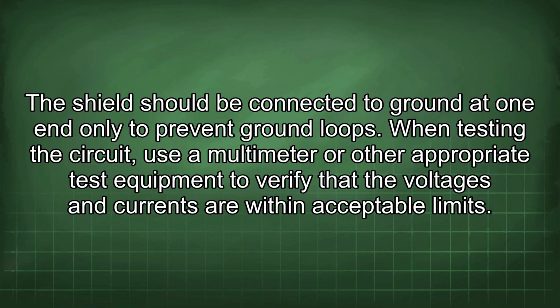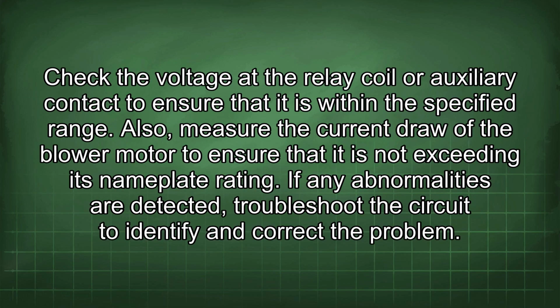When testing the circuit, use a multimeter or other appropriate test equipment to verify that the voltages and currents are within acceptable limits. Check the voltage at the relay coil or auxiliary contact to ensure that it is within the specified range. Also, measure the current draw of the blower motor to ensure that it is not exceeding its nameplate rating. If any abnormalities are detected, troubleshoot the circuit to identify and correct the problem.